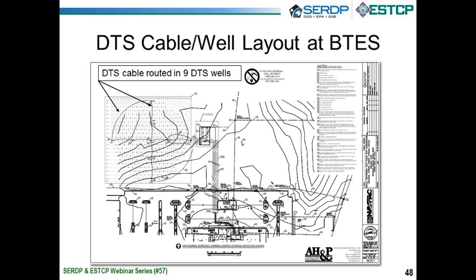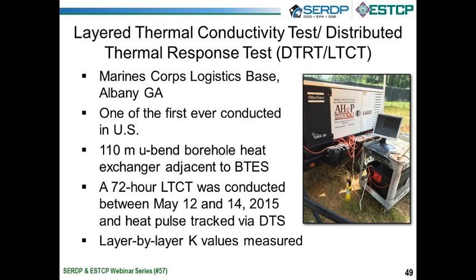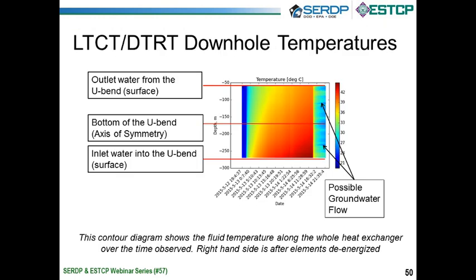In the upper left corner is the BTES. The curvy lines represent the fiber that we weaved in and out of 9 wells. And then we also carried it back to the building so we could monitor the system. We also put some of this fiber down a hole where we do a thermal conductivity test, and it allowed us to measure the thermal conductivity layer by layer. So I won't get into exactly, but this slide represents the temperatures in the U-bend as we tested it. The bottom line is that DTS used in conjunction with a traditional thermal conductivity test will allow you to know the K values of the conductivity layer by layer to optimize the depth of a borehole. It's kind of like getting 6 or 10 thermal conductivity tests for every one you do.